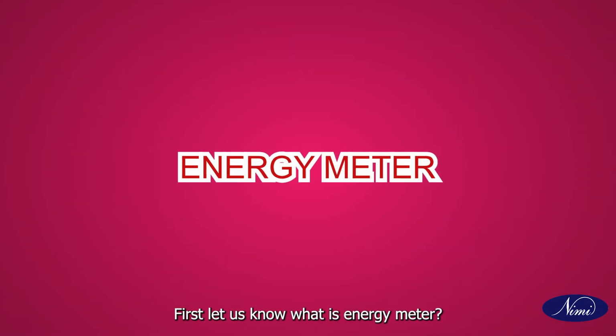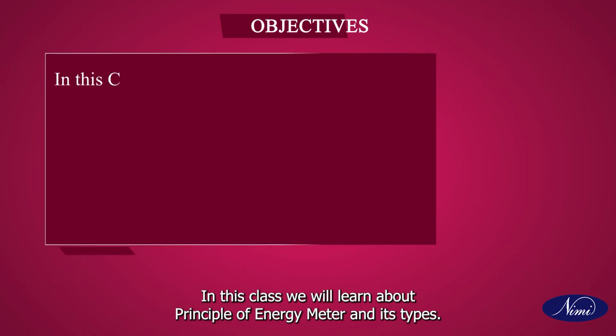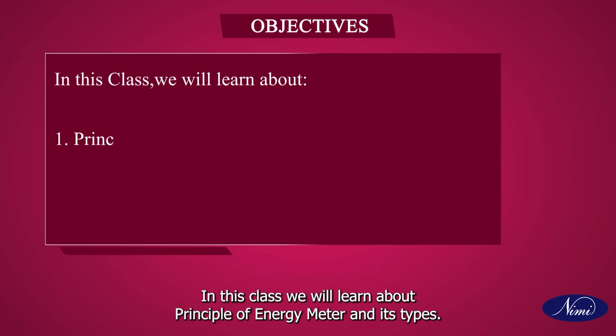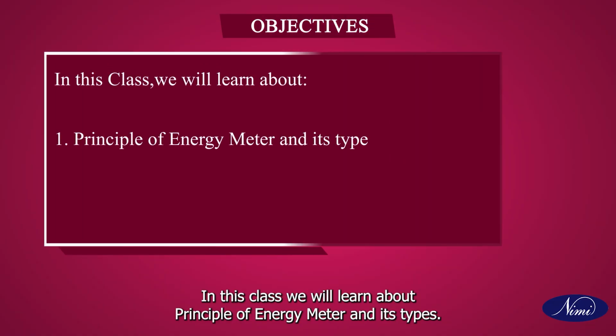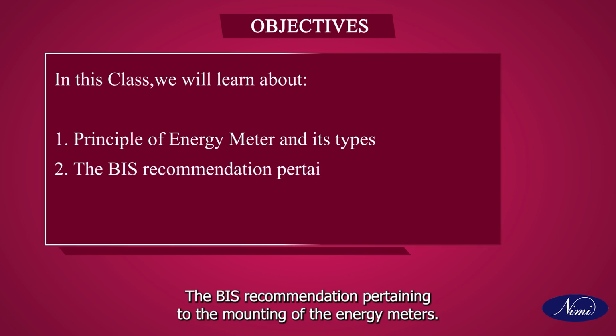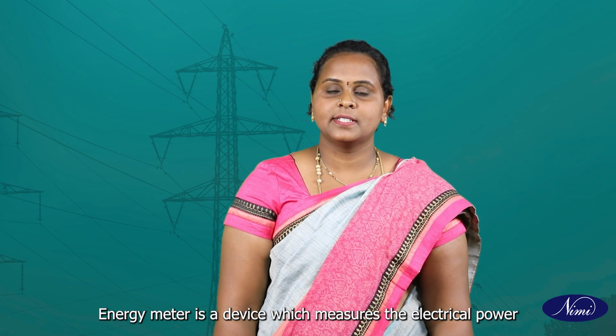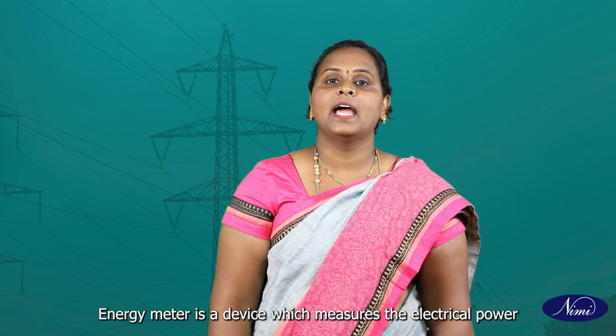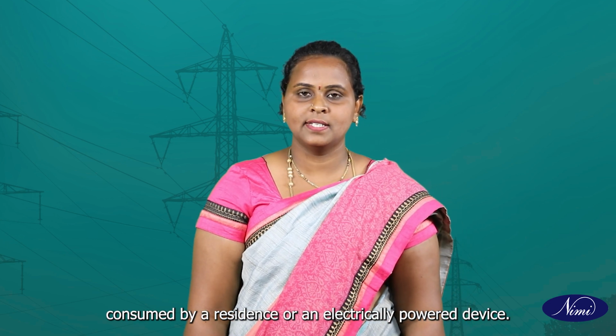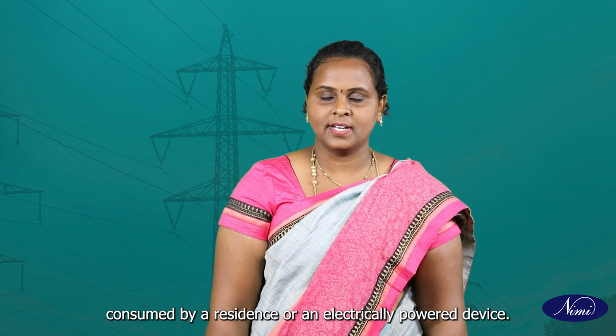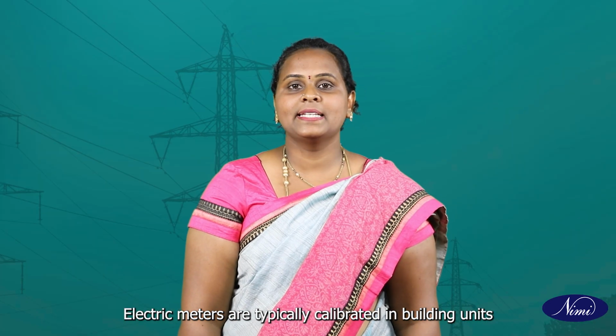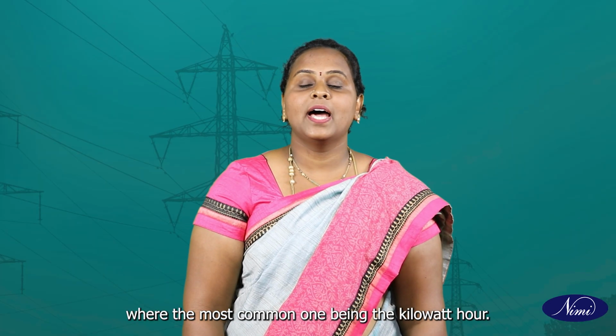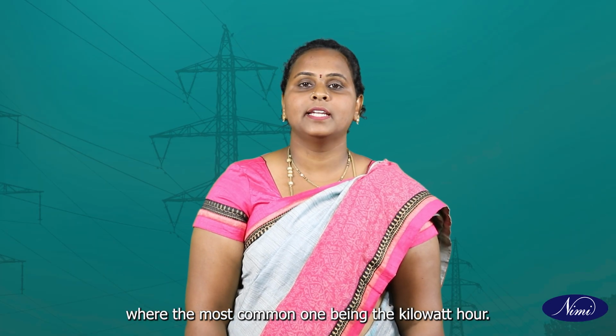First, let us know what is energy meter. In this class, we will learn about principle of energy meter and its types, the BIS recommendation pertaining to the mounting of the energy meters. Energy meter is a device which measures the electrical power consumed by a residence or an electrically powered device. Electric meters are typically calibrated in billing units, the most common one being the kilowatt hour.